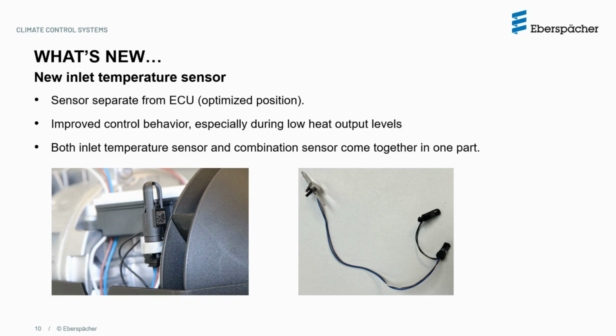Now we have a new inlet temperature sensor that is separate from the ECU for an optimized position, allowing an improved control behavior of the heater, especially during low heat output levels. It sits in the blower motor assembly and can be easily removed and reinstalled as needed by 2 clipping tabs.